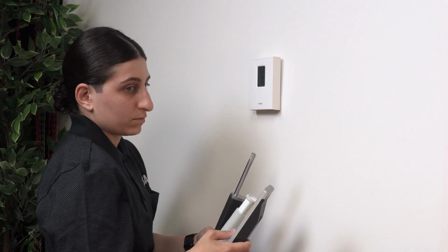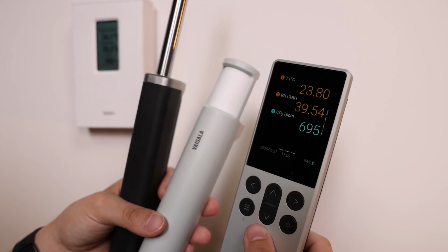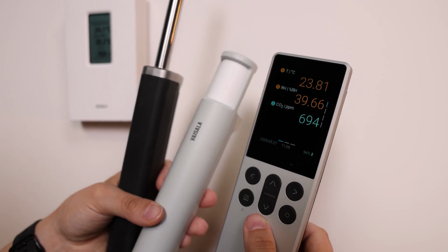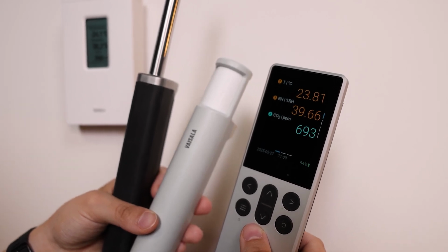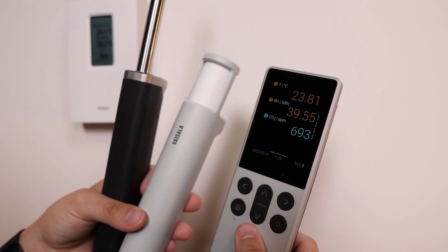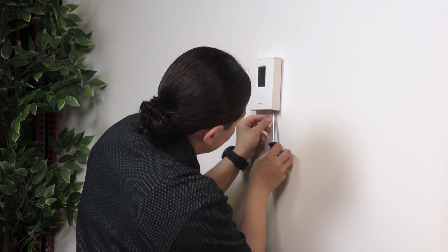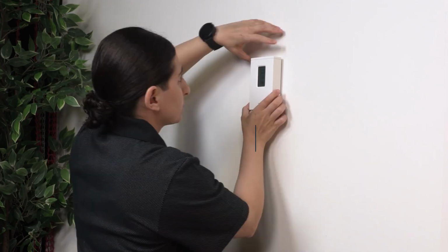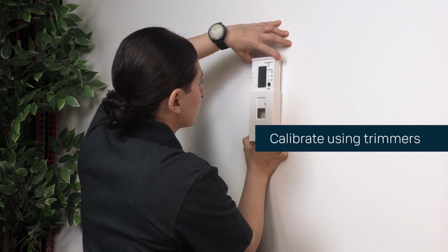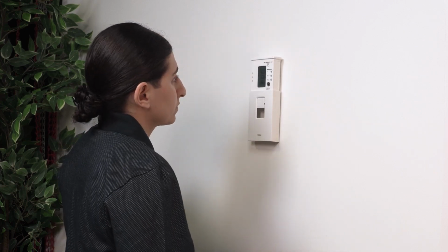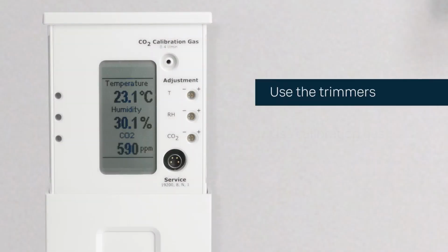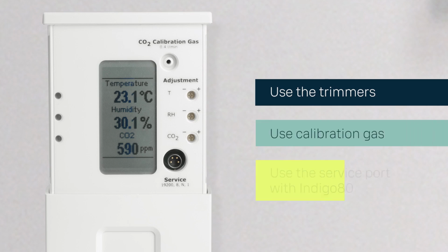To maintain the optimal performance of the instrument, you can choose from several convenient calibration options. Compare the readings with any reference device. If you need to adjust the unit, remove the screw, slide down the cover, and use the offset trimmers. You can adjust the measurements by using the trimmers, calibration gas, or the service port with Indigo 80.